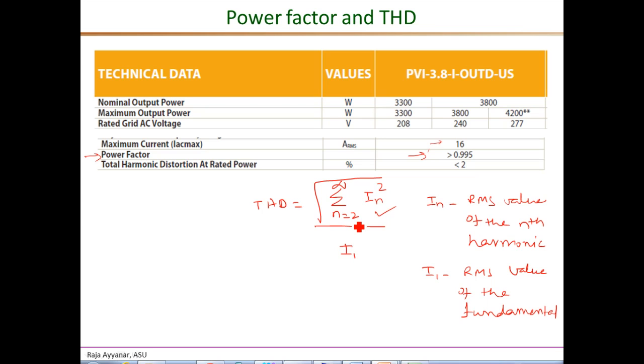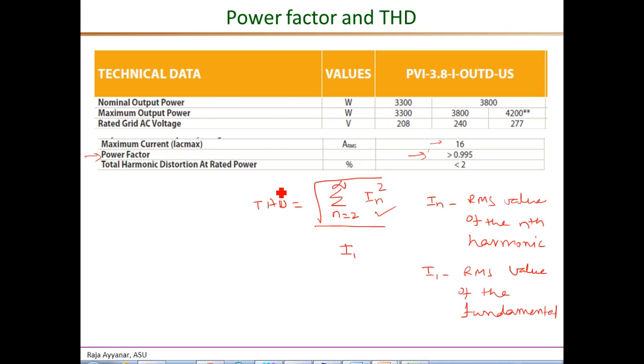The switching frequency content is independent of the magnitude of the fundamental component of the current — that is, independent of the active power injected into the grid. Therefore at lower power injection, say half of the rated power under lower solar irradiance, the high-frequency content in the numerator remains fixed while the denominator comes down by a factor of 2, making the THD ratio twice that specified at rated power. However, this may not be a problem because what finally matters for power quality of the distribution system is the absolute value of the harmonic component, which does not increase with reduced power injection.